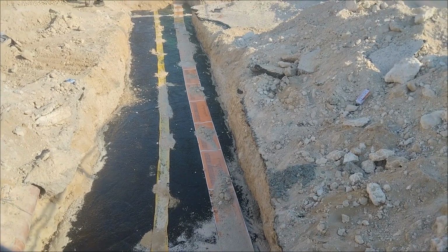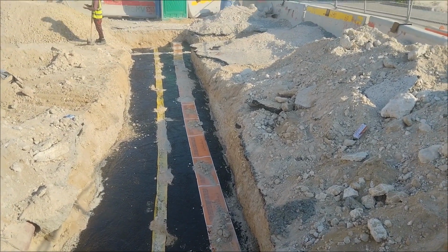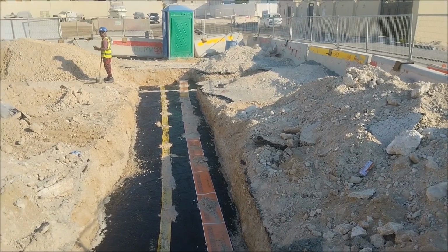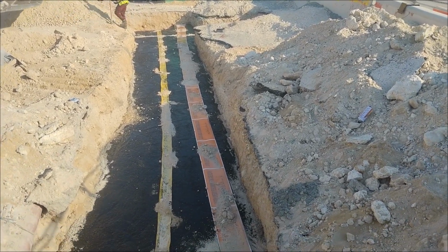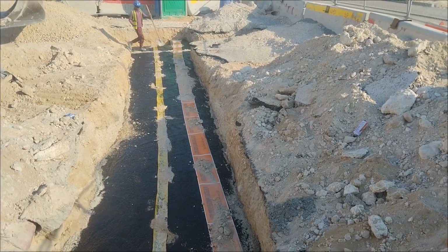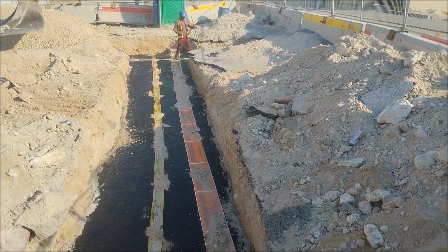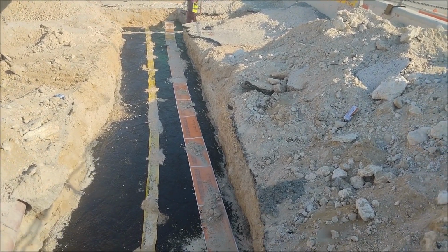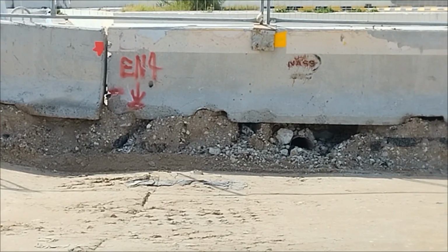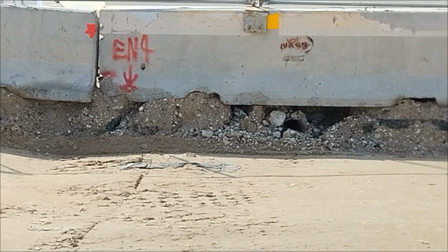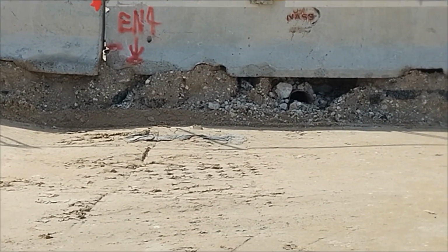As you can see in this clip, the concrete surrounding is almost completed. Bitumen coating is done on the road crossing duct. Warning tape is almost installed because two utilities are passing through this area. So different types of warning tapes from an approved source should be used here. After the warning tape installation, this area will be backfilled to reach up to the subgrade bottom level.